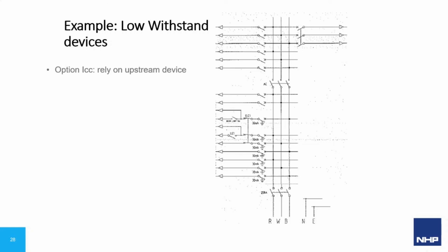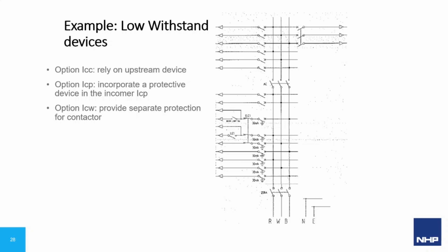We could apply a conditional withstand rating. This would require us to stipulate a specific upstream device that could lend protection to our contactor. If this is not possible, the next option would be to use the ICP rating. This would require we replace the load break style contactor with a protection device. The last option is we can use the ICW rating. However, this would require that a separate protection device for the contactor be installed in our system downstream of our incoming load break switch.